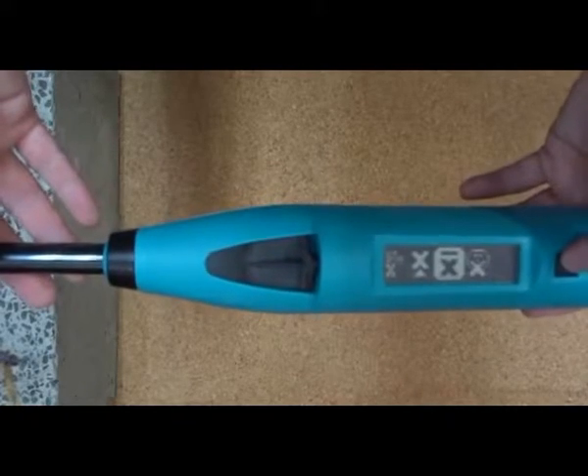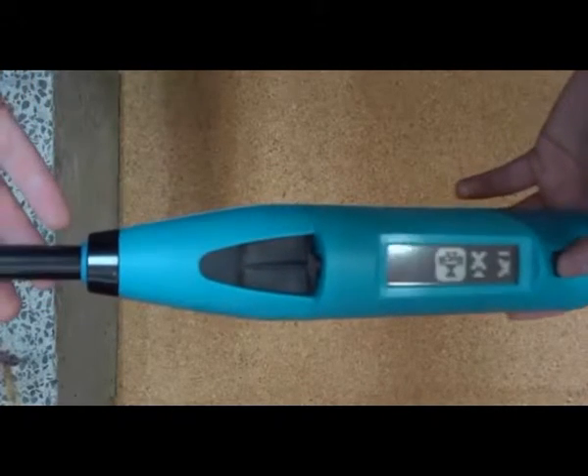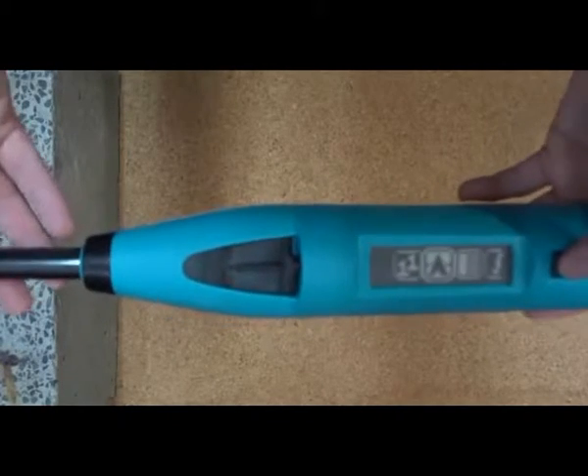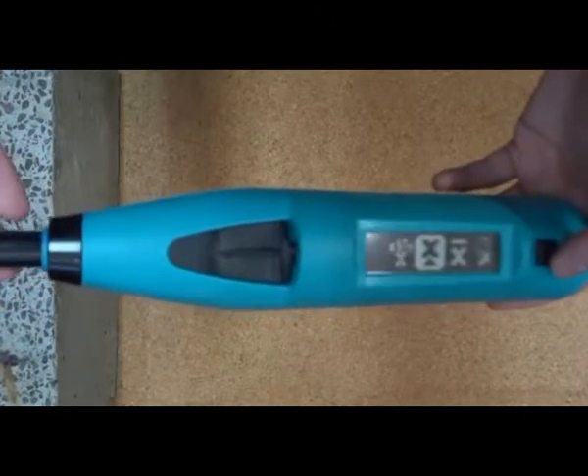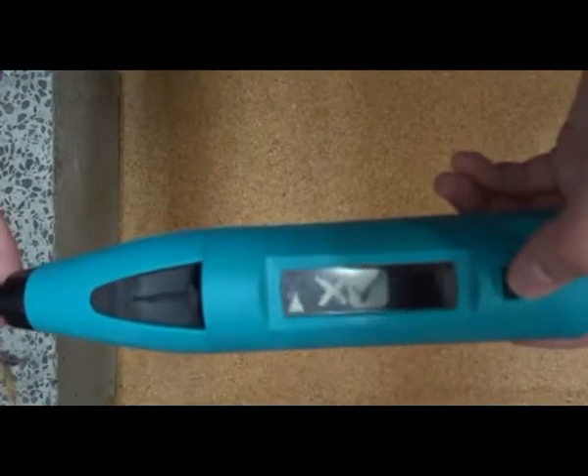When we want to set up to use the hammer for actual testing, we'll select an averaging method. We don't want the ASTM one, we're going to use the custom one, which I'll demonstrate how to set up a little bit later. So that's the custom curve selection, and we just select that.